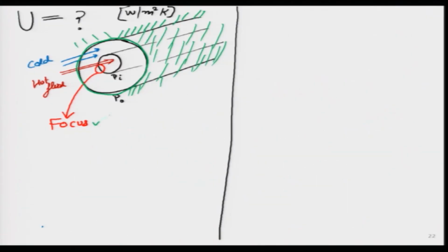For instance, if you look at the condenser outside, the unit which is placed outside, you do not see any insulation over there, because the fluid that we are trying to heat is the air itself. In those special cases we do not put it, but in general we will definitely put it over there, which gives us the main focus on this particular inner pipe, because this material is very, very important. Generally speaking, the rule of thumb is we use a very high thermal conductivity material to make this inner pipe. So, usually we can use copper or aluminum.